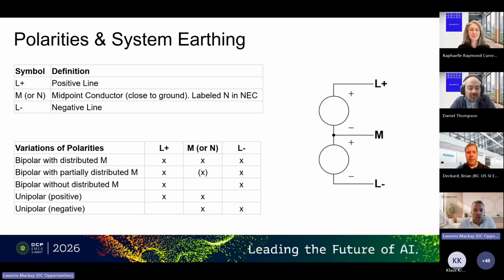And then here on the right, there are different variations on how we can use these conductors. On the right side, we see a bipolar system with a plus pole, a midpoint, and a minus pole. That's the most complete system, and then we can have different variations of it. For example, we can distribute this middle conductor all the way. Then we have a bipolar system with distributed M. We can distribute it to some of the loads, for example, some loads are connected to it. Some loads are connected directly between the plus and the minus. Then you can leave away the middle conductor. That's the same thing as we sometimes do in three-phase AC for big loads.